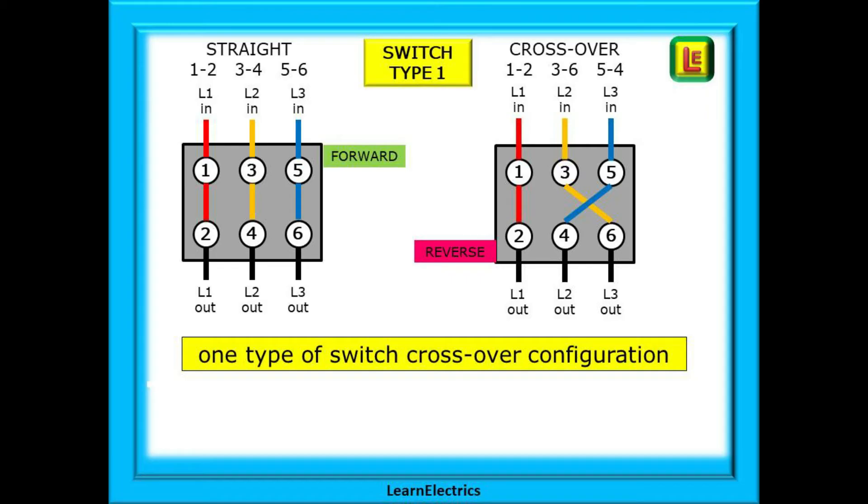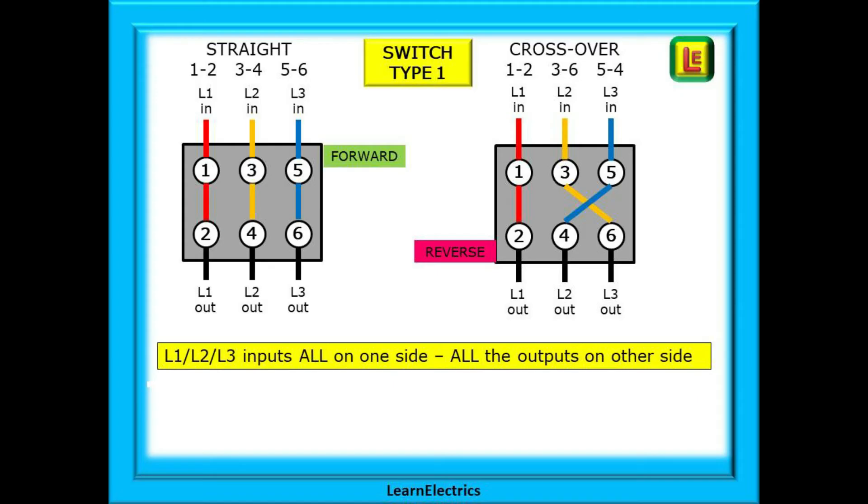With type 1 switches we can have straight through connections 1 to 2, 3 to 4, 5 to 6 for forwards, and for reverse in this switch 1 still goes to 2, but 3 crosses over and goes to 6, whilst 5 crosses over and goes to 4. Notice that the incoming phases L1 in, L2 in, and L3 in are all on one side of the switch, and the output wires to the motor L1 out, L2 out, and L3 out are all on the other side.